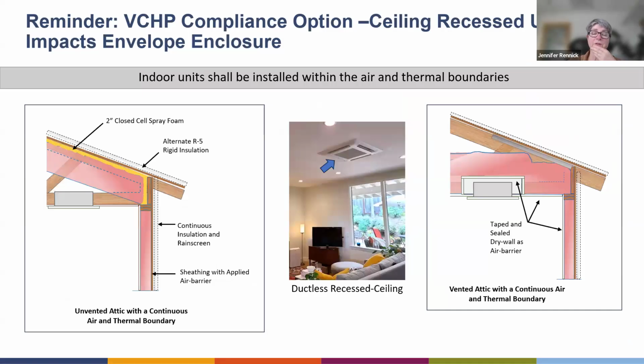The unit itself, the indoor unit, needs to be within the air and thermal boundary. How that can look if you're doing a ceiling recess is to either put the insulation at the top of your attic space and have potentially an unvented attic. Or if you have a vented attic, you can create a box that goes over and around that recessed ductless unit. You can tape and seal that drywall box and have it be a continuous air barrier with the drywall ceiling and drywall walls.